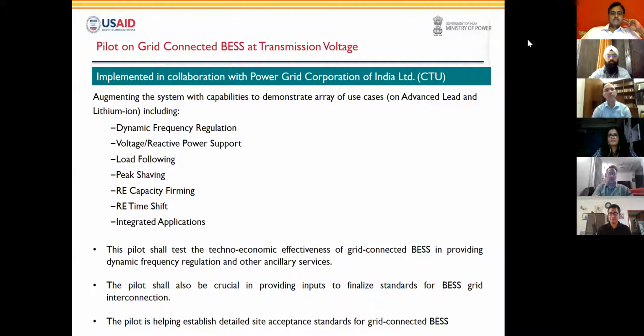Our help was provided to enable a range of use cases, from dynamic frequency regulation to reactive power support, load following, peak shaving — seven or eight use cases, all enabled on the existing system by revamping the controls of the battery system there. We are going to commission this fairly soon. It's still delayed a bit because of the current situation, and a lot of the deliveries, or one of the components, was coming from China, so it got a little interrupted, but we are ready for testing on the ground.